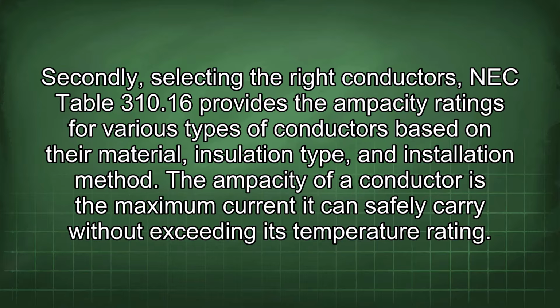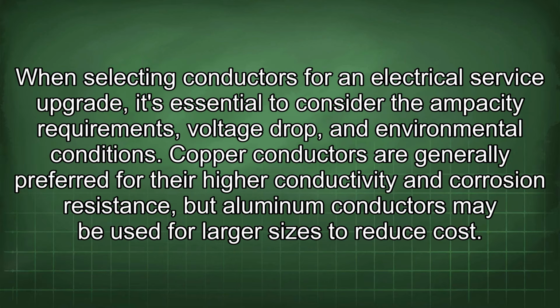Secondly, selecting the right conductors. NEC Table 310.16 provides the ampacity ratings for various types of conductors based on their material, insulation type, and installation method. The ampacity of a conductor is the maximum current it can safely carry without exceeding its temperature rating. When selecting conductors for an electrical service upgrade, it's essential to consider the ampacity requirements, voltage drop, and environmental conditions.